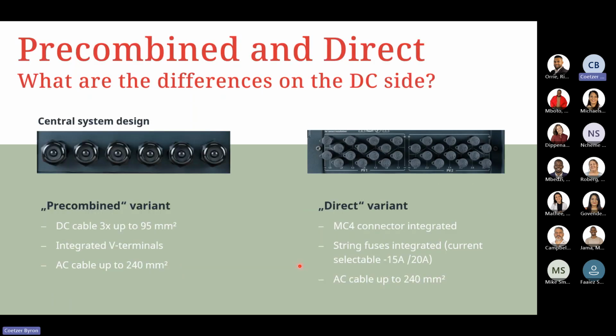So what are the differences on the DC side? On your central system design, on the pre-combined variant, you'll have 3 glands that can accommodate up to 95 mm² cable coming through. You've got integrated V clamps and V terminals mounted on the DC side for the fixing of the cable, and we can have cable up to 240 mm², depending on what variation we are using.